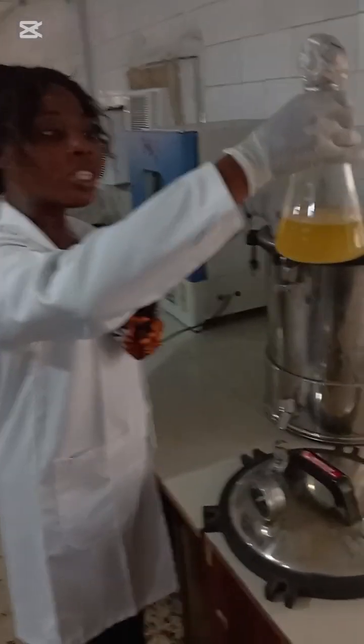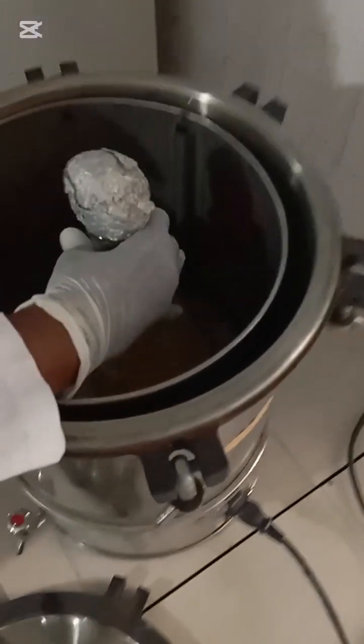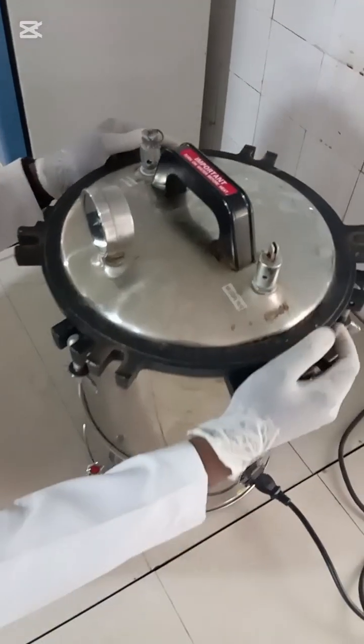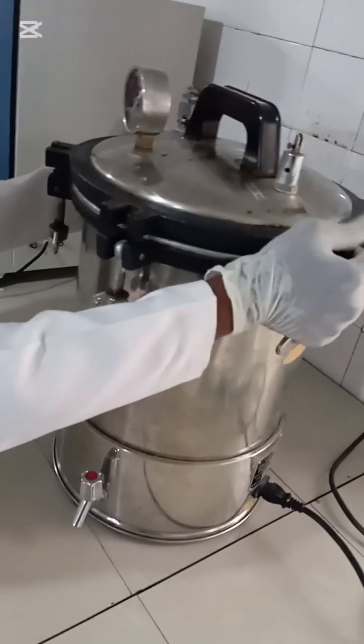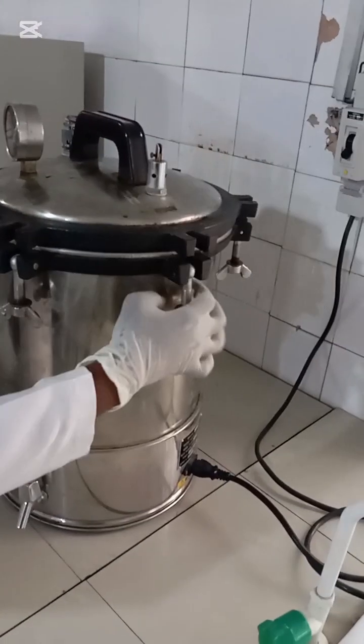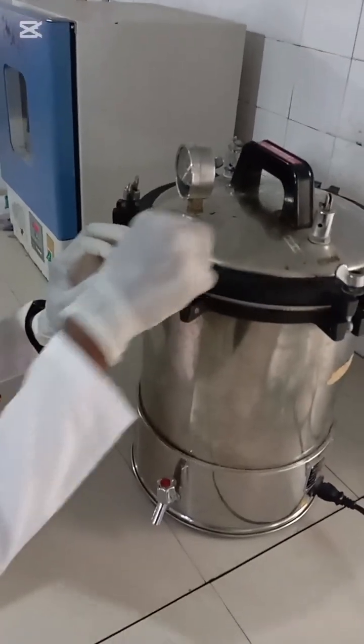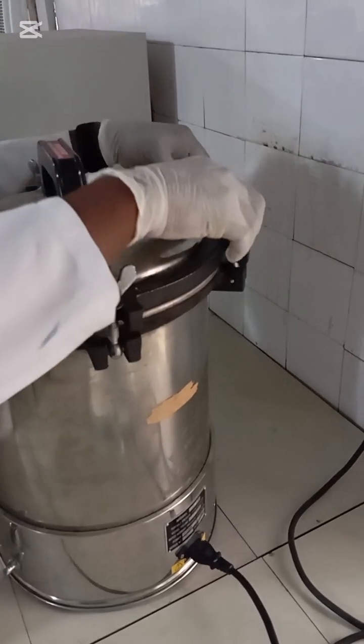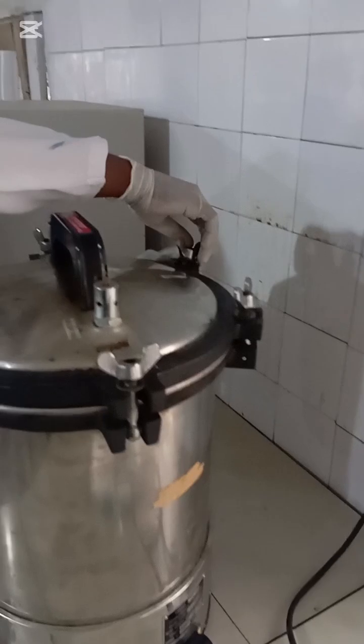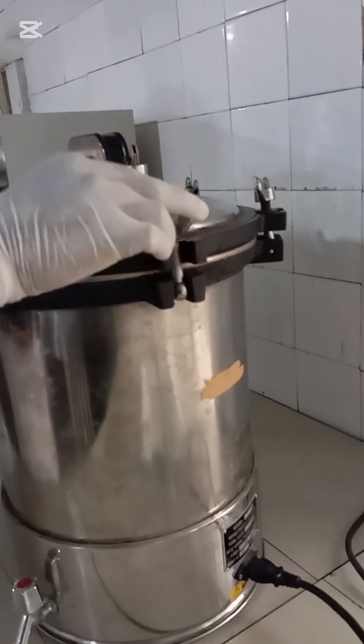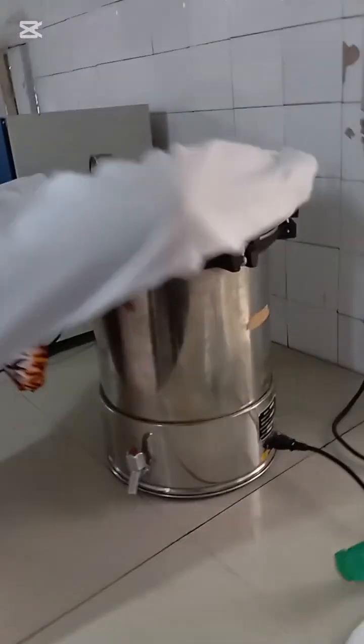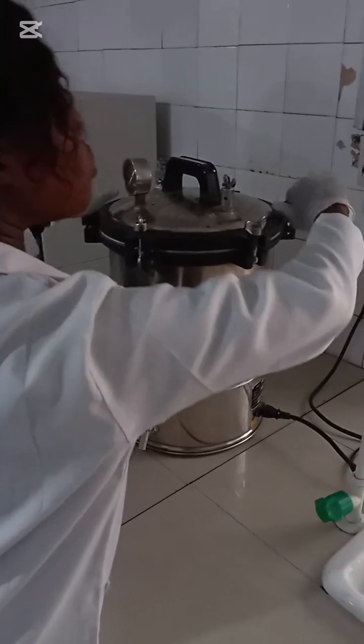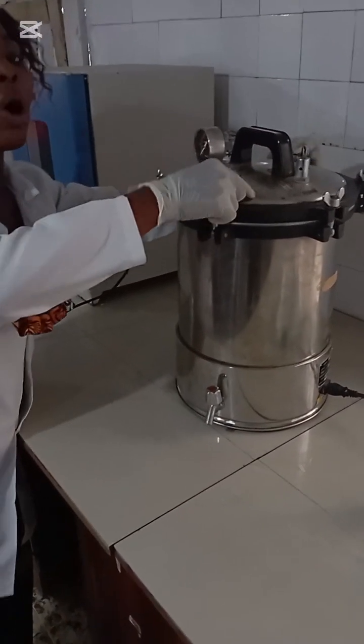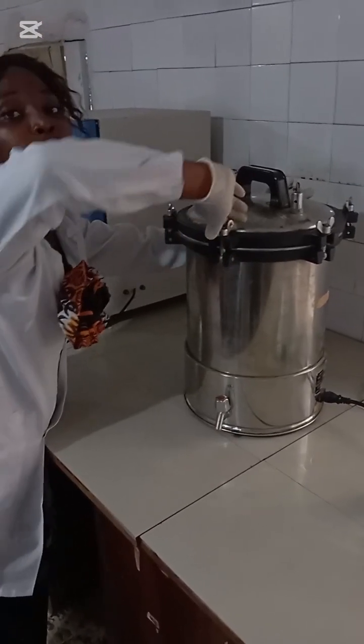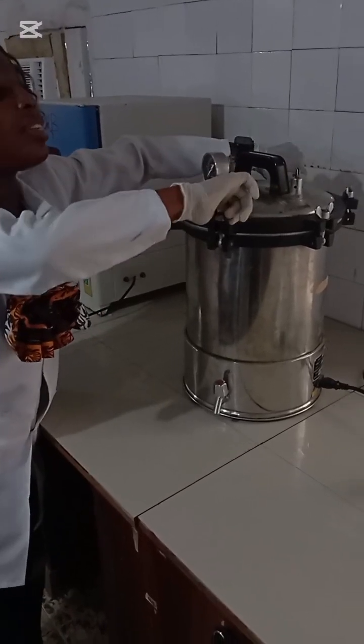So now we'll put the conical flask containing our agar inside the autoclave basket. Place it like this, and then you cover with the lid. Now to seal, we seal at opposite directions. That is, first put the knot. So these are instruments of sterilization. Now the autoclave uses moist heat sterilization. So you see I'm sealing at opposite directions like this. At increased pressure, the temperature of water goes beyond 100 degrees Celsius to give you steam that will penetrate into the items that you want to sterilize or autoclave. So it uses moist heat sterilization.